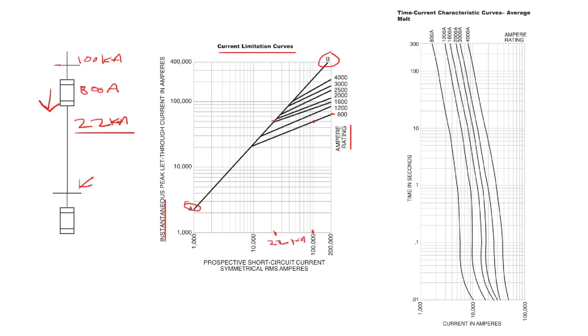This fuse is providing two different types of protection to the system downstream. One, it's limiting the let-through fault current, and two, as we discussed, it'll also be disconnecting the circuit from the system after a given time.